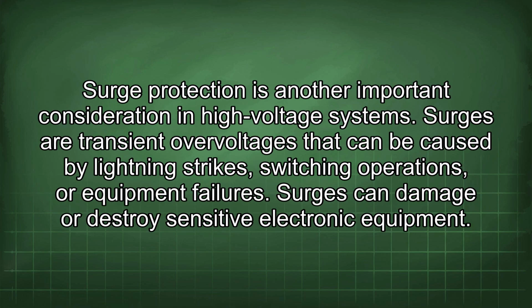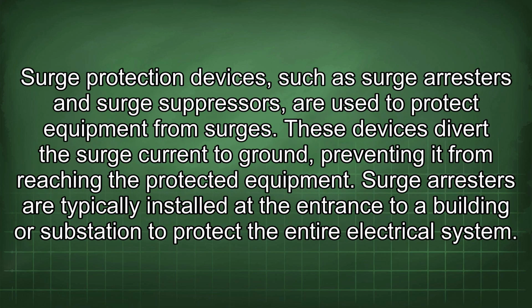Surge protection is another important consideration in high voltage systems. Surges are transient overvoltages that can be caused by lightning strikes, switching operations, or equipment failures. Surges can damage or destroy sensitive electronic equipment. Surge protection devices, such as surge arresters and surge suppressors, are used to protect equipment from surges.